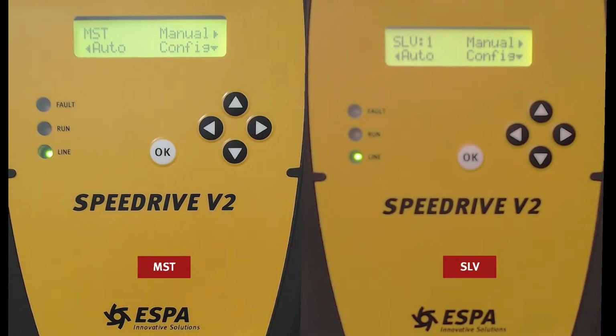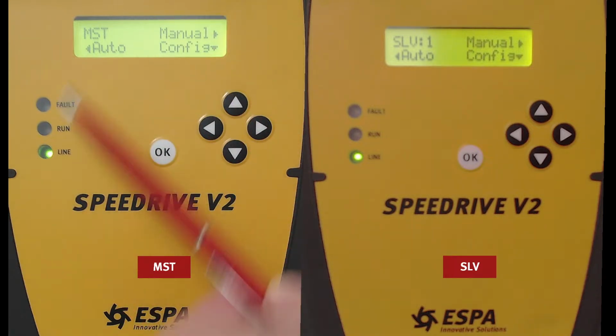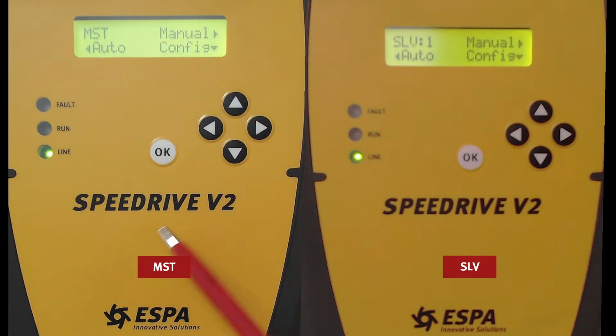These are the initial screens in both Speedrive. This one is the master pump, and this one the slave. We have one master pump which controls all the other slaves. With the master pump we can control up to 7 slaves. So we just have to configure the master one, and it will send all the orders, parameters and settings to the other pumps.